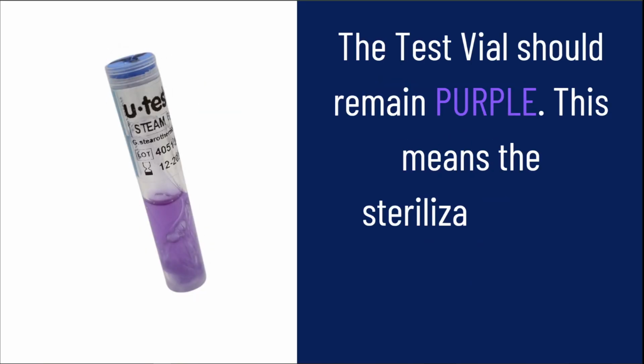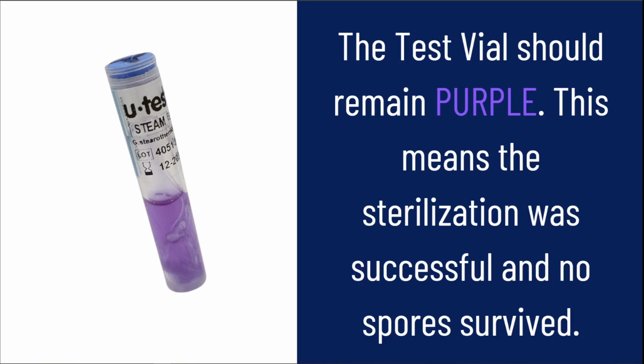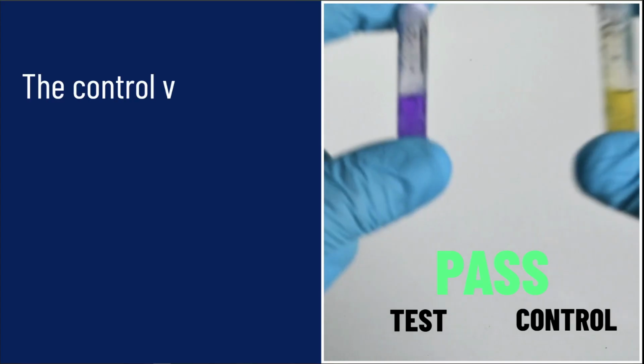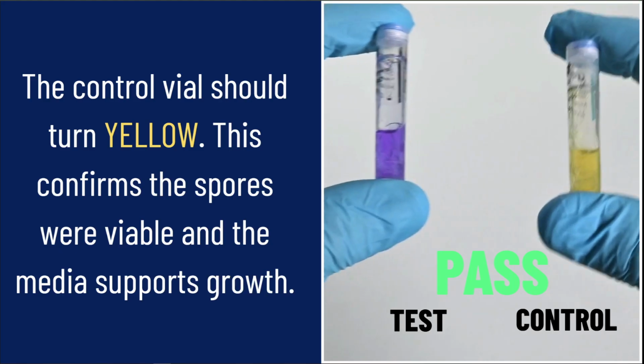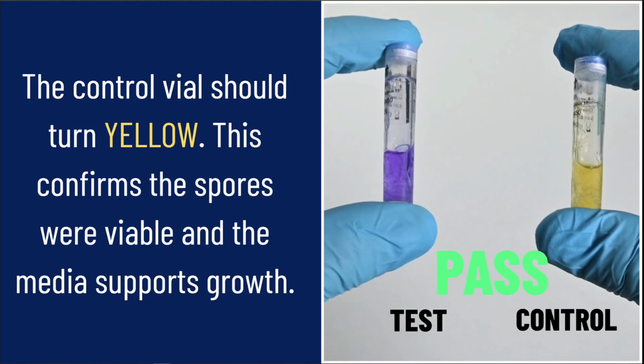The test vial should remain purple. This means the sterilization was successful and no spores survived. The control vial should turn yellow. This confirms the spores were viable and the media supports growth.